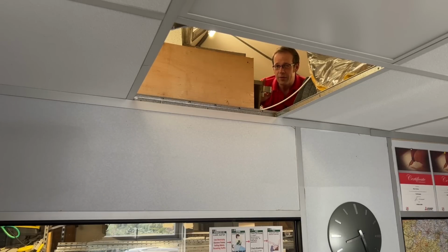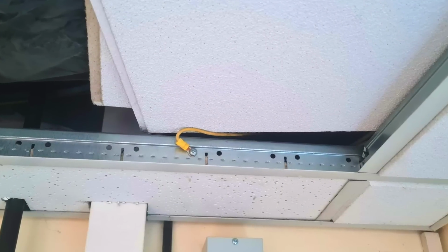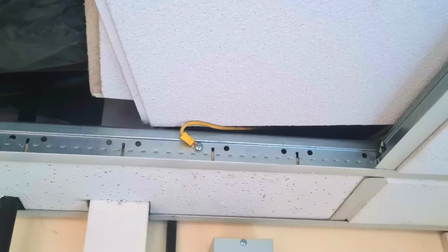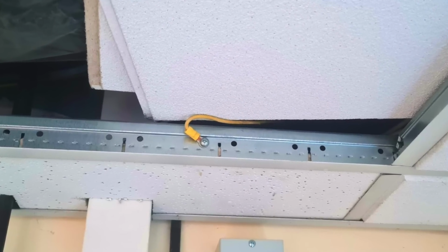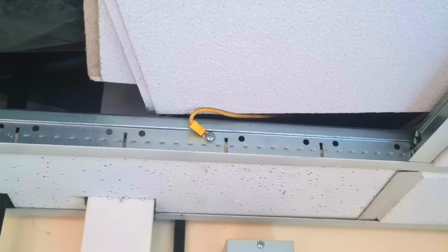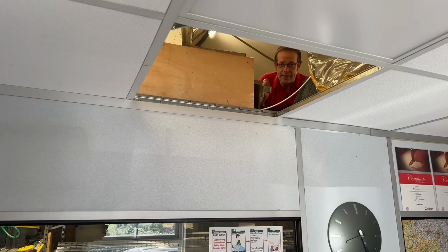But let's think about this question. You do see it from time to time, don't you? Especially on older installations where a connection has been made from the earth terminal of a lay-in light fitting to the grid of the suspended ceiling. And sometimes it's taken even further, and the L bracket around the side has a green and yellow link from one piece to another in the corner. But is any of this necessary?